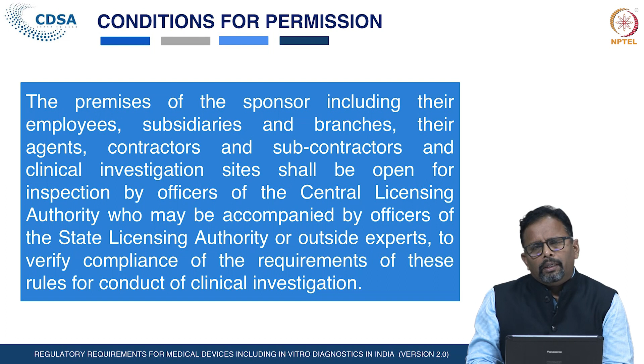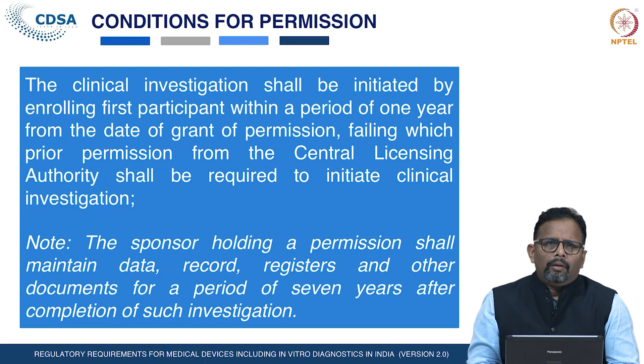The clinical investigation shall be carried out by enrolling the first patient within a period of 1 year from the date of grant of the permission, failing which prior permission is again required to be obtained by the applicant from the Central Licensing Authority. The sponsor holding the permission shall maintain the data, records, registries, and other documents for a period of 7 years after completion of such investigation. These are the conditions of the clinical investigation permissions obtained from the Central Licensing Authority.